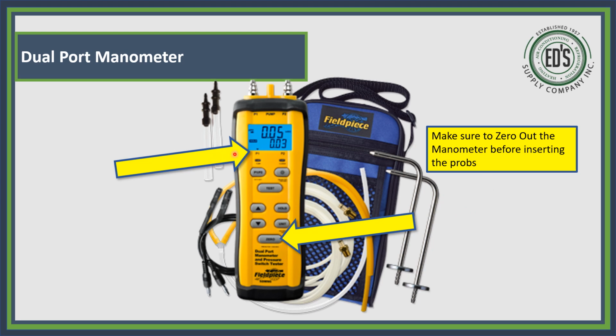So we want to recap, and I want to show you something real quick. Here's what I use out in the field. I have this dual manometer. Here's my zero out button. Make sure you zero out the manometer before you insert the probes, okay? I take this plastic tubing, I put them on here, and I put them on this ductwork. This was for testing your velocity or your speed of your ductwork. The yellow tubes go with these to check my gas probe or my gas pressure.